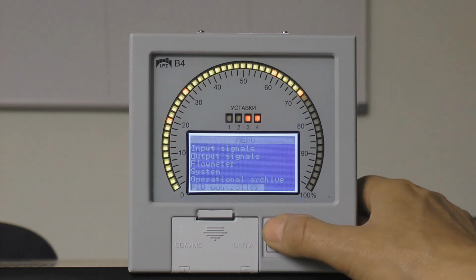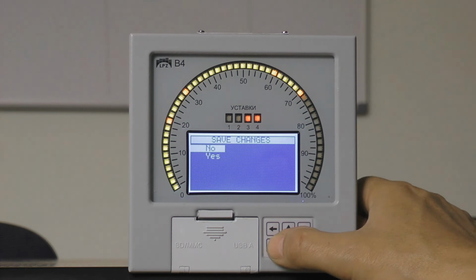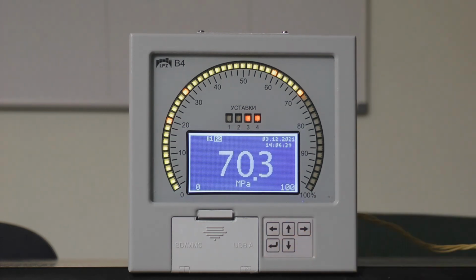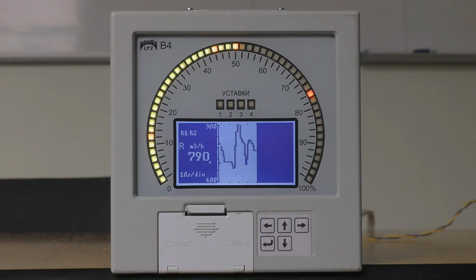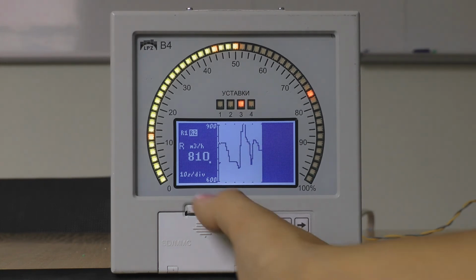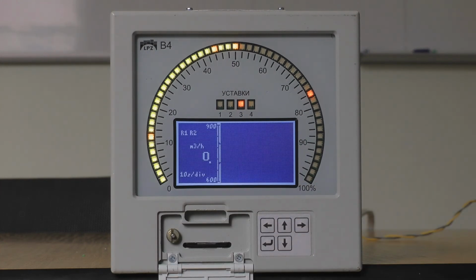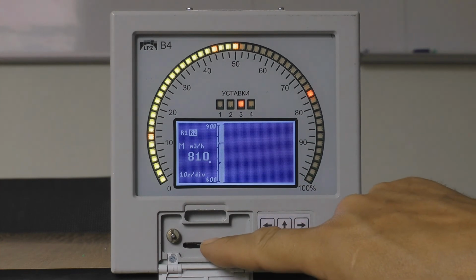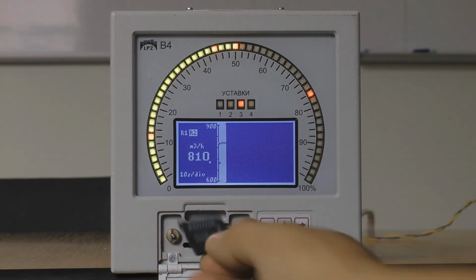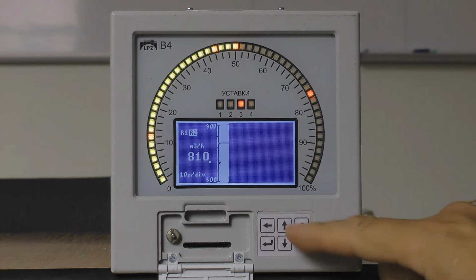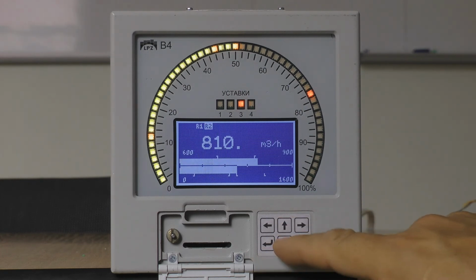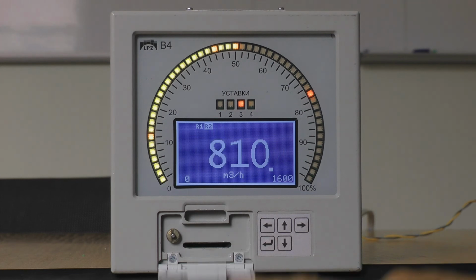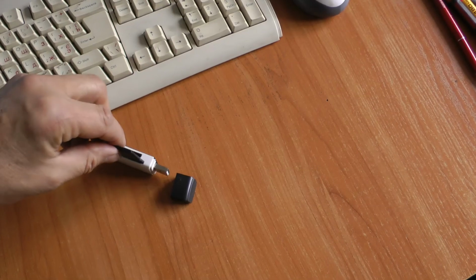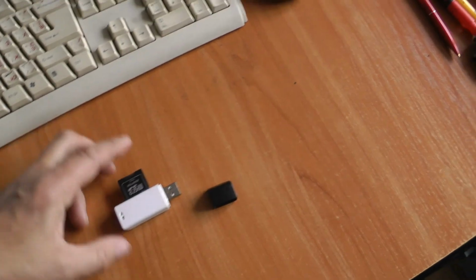We will skip PID controller, and when we deal with all the settings, the system will ask us if we want to save changes. I want to finish the overview of the instrument with the information about the permanent archive, which is stored on SD card of the instrument. If you open a slot and extract the SD card, you can copy the archive on your PC and view it there. As you can see, the instrument works even without SD, with the operational archive only. We put the SD card in an adapter and connect it to your PC.